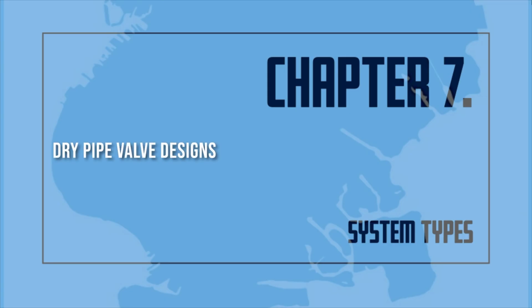Dry pipe valve designs. These valves prevent water from flowing into the piping until a sprinkler head has opened. The air pressure in the system keeps the clapper closed. This clapper prevents the water from flowing into the system. When the sprinkler head opens, it causes a drop of pressure in the piping. This causes the valve to open and allows water into the system. Most dry pipe valves are designed so that a moderate air pressure in a dry pipe system will hold back a much greater water pressure. When the clapper has opened, the valve is said to have tripped.